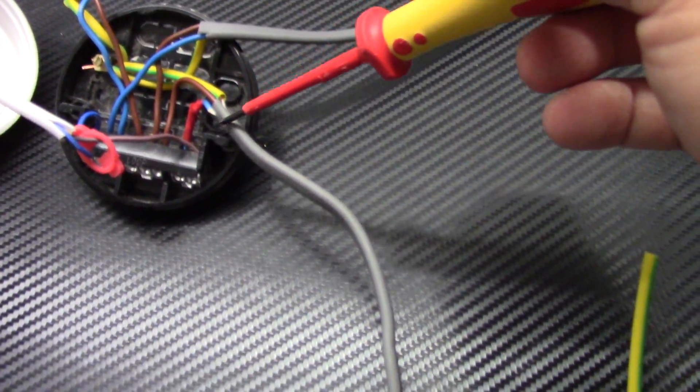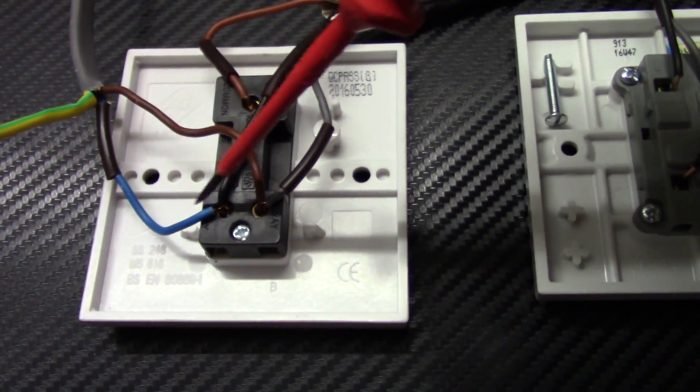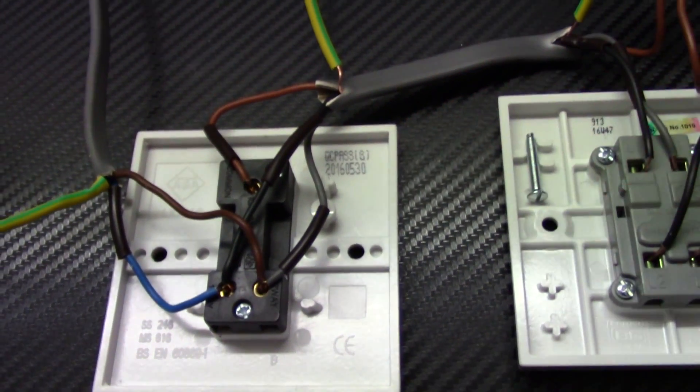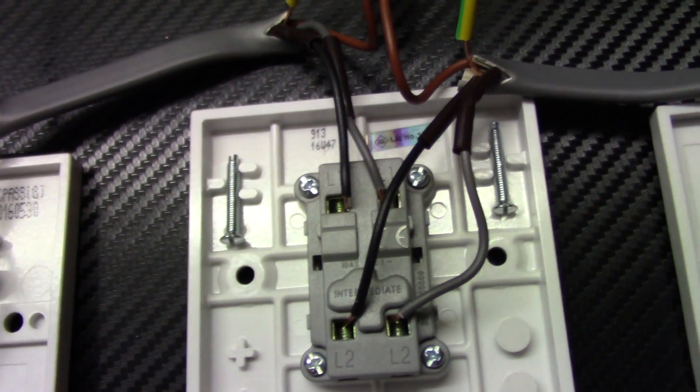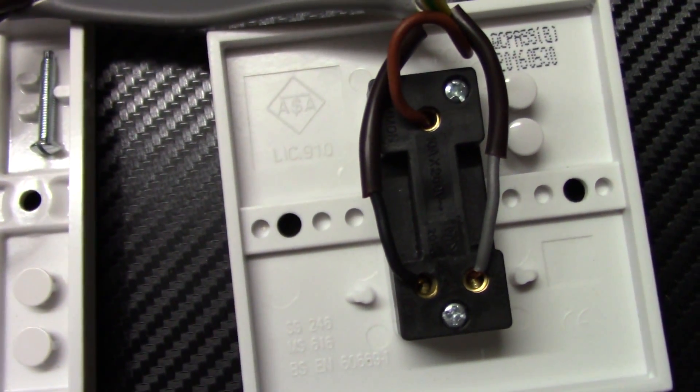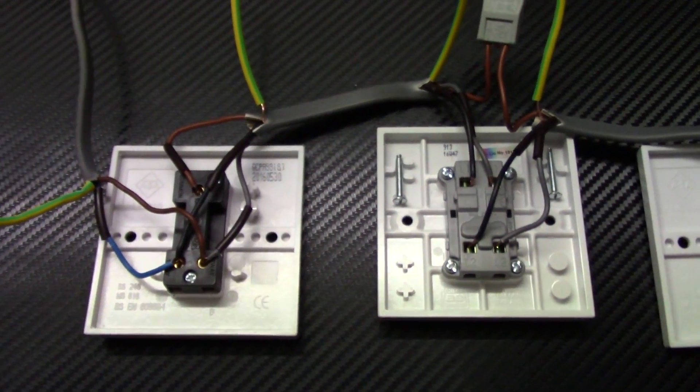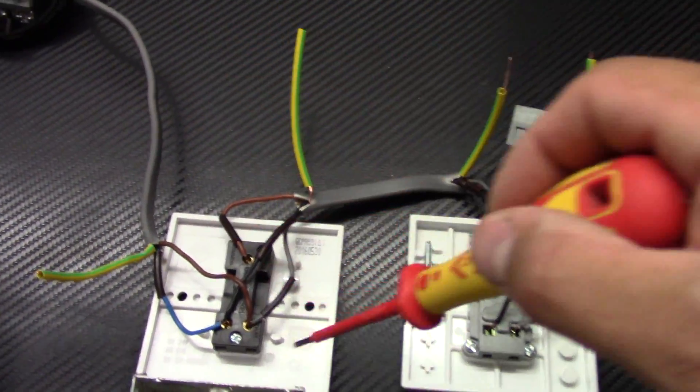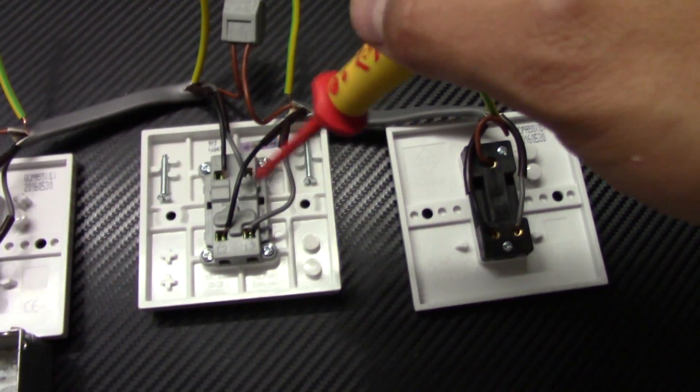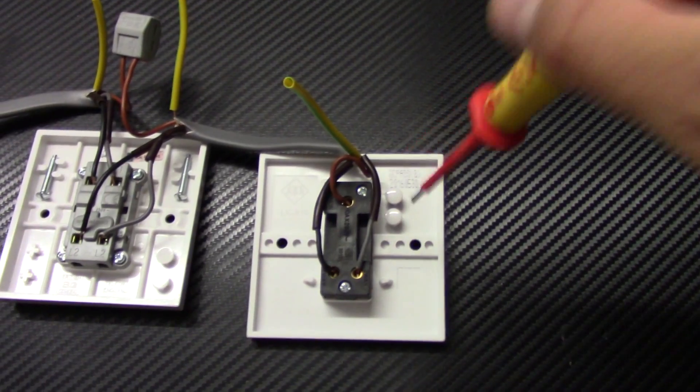So cable from the ceiling rose. Live wire to L2. Switch live to the L1. There's an earth terminal here. So we connect these two wires in one back box into earth terminal. These two wires also in the back box for the intermediate switch. And at the end we've got just one earth wire. So we connect to the back box terminal in this switch.